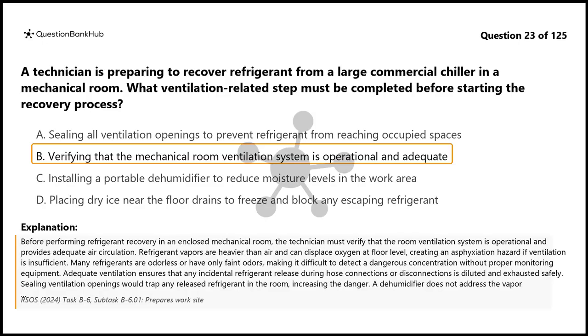Before performing refrigerant recovery in an enclosed mechanical room, the technician must verify that the room ventilation system is operational and provides adequate air circulation. Refrigerant vapors are heavier than air and can displace oxygen at floor level, creating an asphyxiation hazard if ventilation is insufficient. Many refrigerants are odorless or have only faint odors, making it difficult to detect a dangerous concentration without proper monitoring equipment. Adequate ventilation ensures that any incidental refrigerant released during hose connections or disconnections is diluted and exhausted safely.